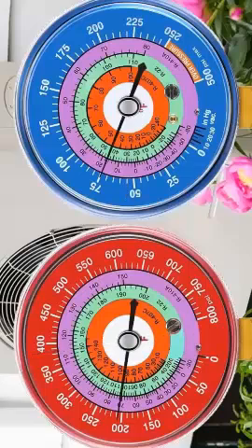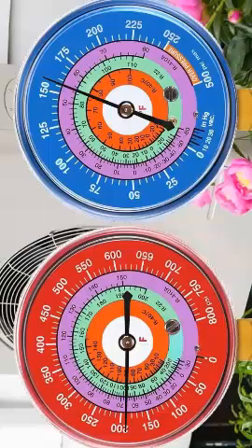E. If, after turning on the unit, both pressures are lower than normal, this may suggest a refrigerant leak, which can be confirmed if the unit's power consumption is significantly lower than usual. F. If the compressor starts but there's no clear difference between low and high pressure, this indicates mechanical failure of the compressor.